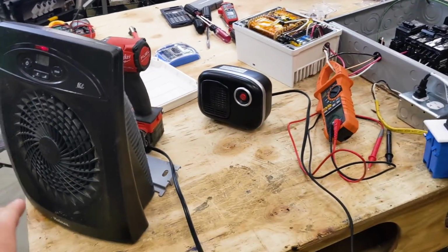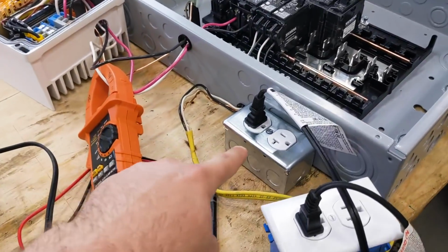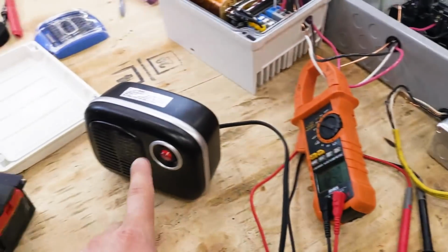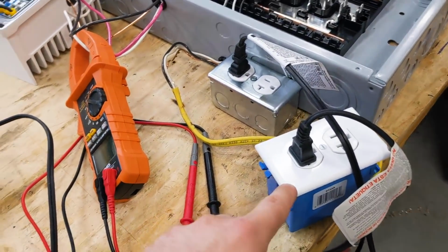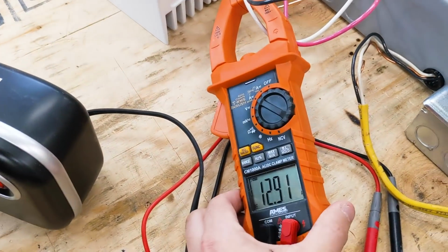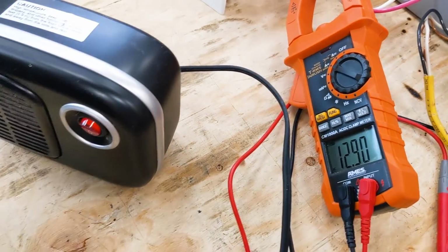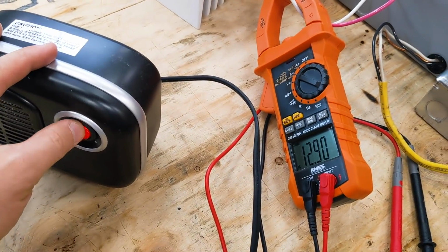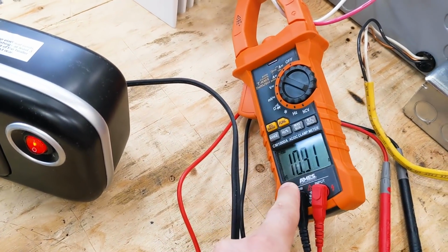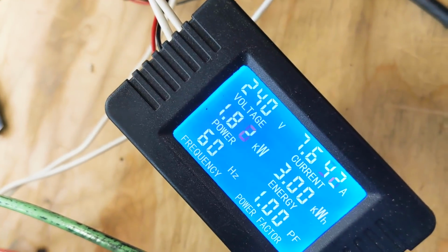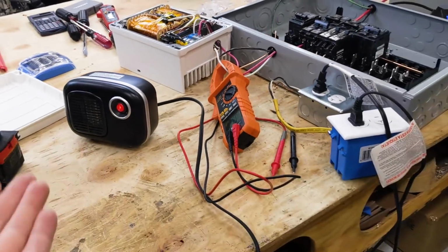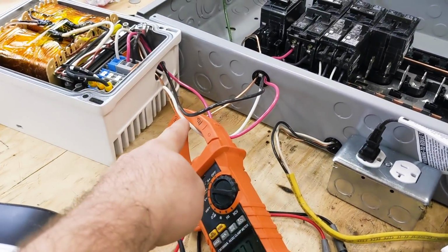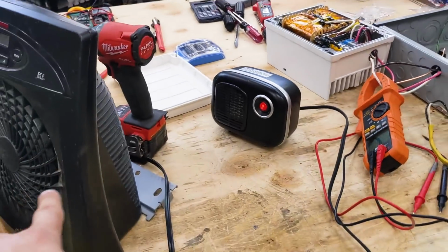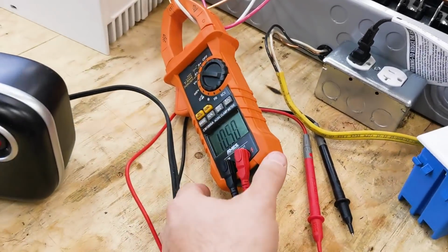Here's where things get really exciting. This heater is plugged in on one phase, and I plug this other little heater into the other phase. Currently, off the neutral, we have 12.9. Now watch what happens when I turn on this other space heater. It drops. But our total watts has gone up, 1.8 kilowatts instead of 1.5. So the total power has gone up, but the load on the neutral has gone down because the two phases are balancing each other out a little bit.